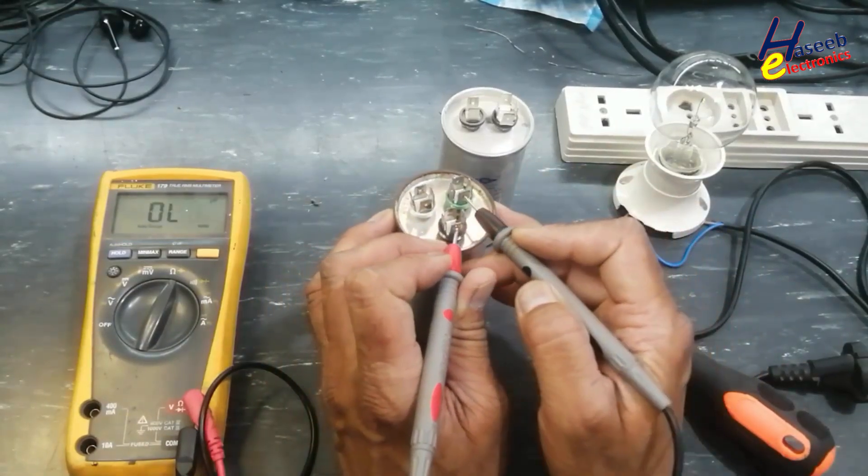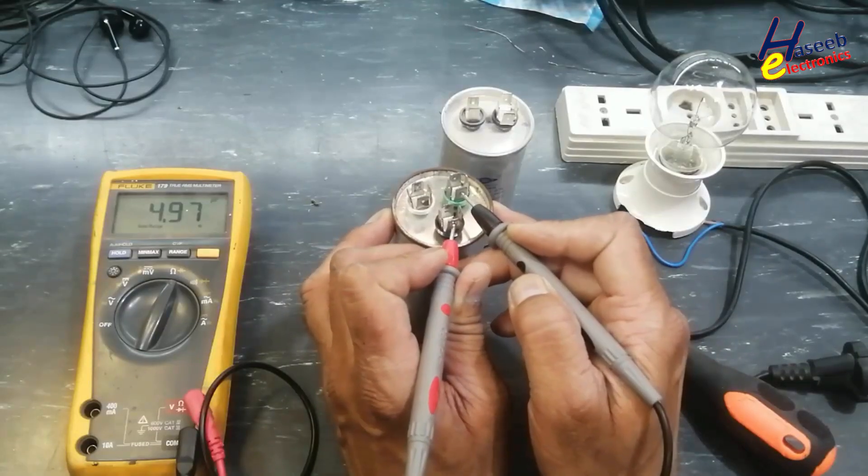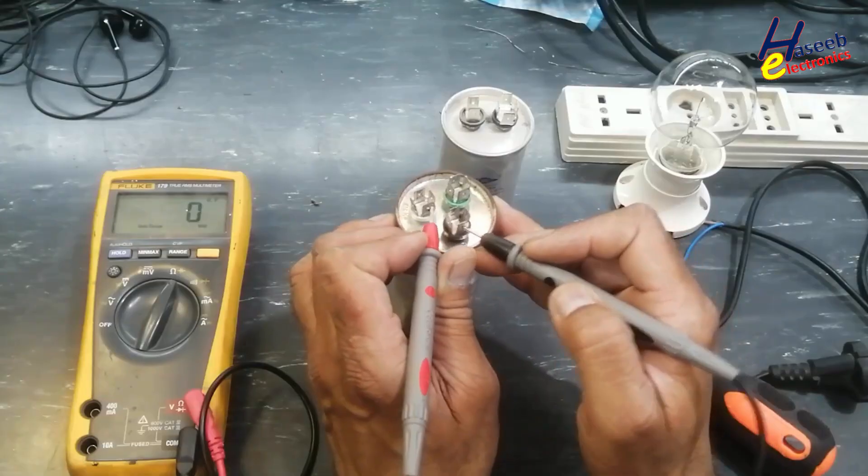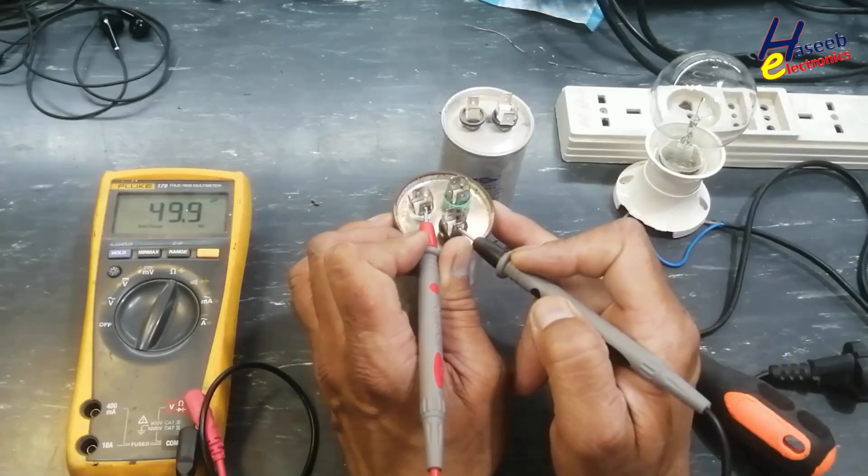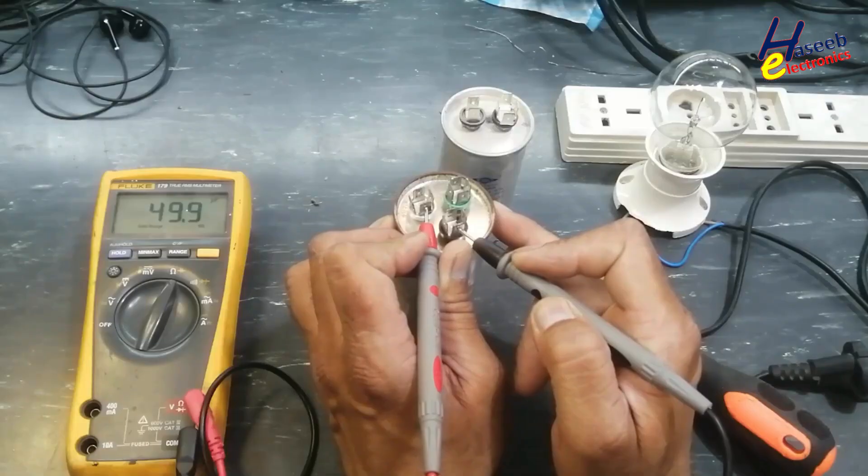Common with fan: 4.97uF, 5uF. It is good. And this 50uF, reading 49.9uF. So it is good.